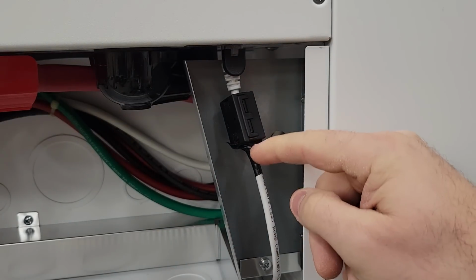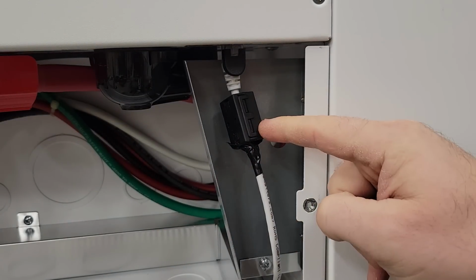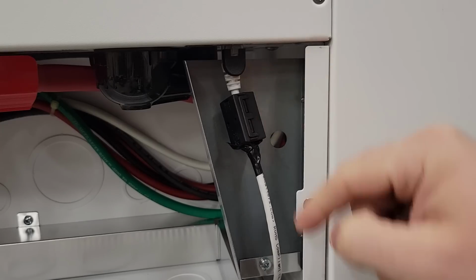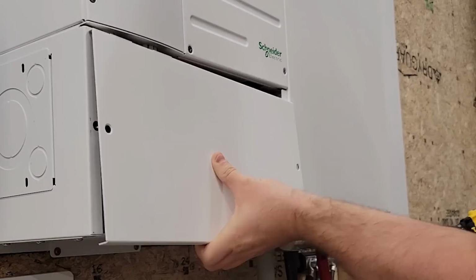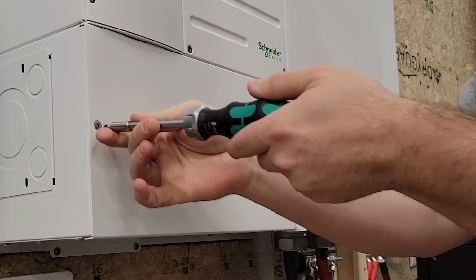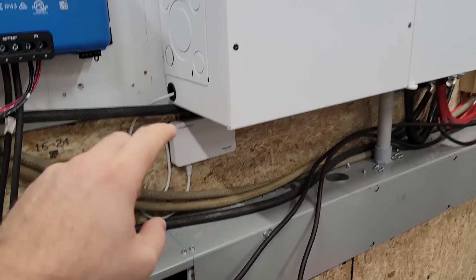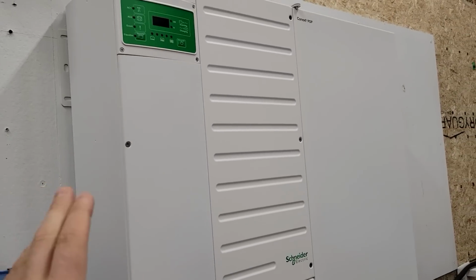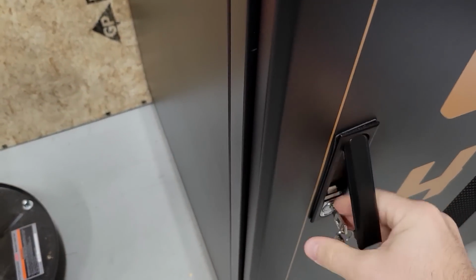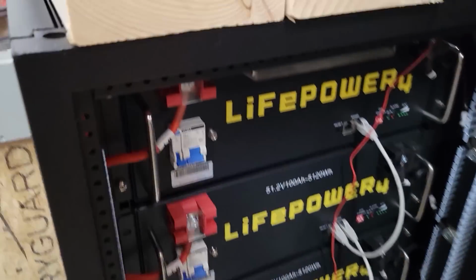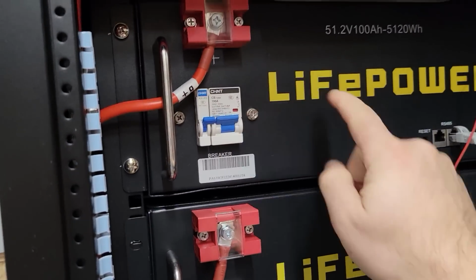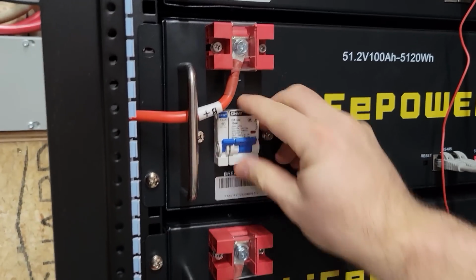There we go. So now it won't slip down. The manual says that this needs to be up close to the inverter. So there we go. The InsightHome is wired in and the inverter is currently off. I've got the big 250 amp circuit breaker on and we're going to turn on the battery now. The batteries have pre-charge resistors built in.